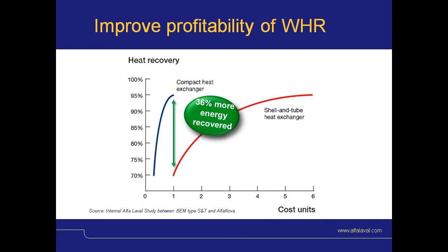Heat exchangers and waste heat recovery play an important role to improve energy efficiency in the process industry. Waste heat recovery means applying heat exchangers to recover energy from process or utility streams and making use of the recovered energy to improve the net energy consumption in a plant. So it means to install heat transfer capacity to capture the energy before it is lost in the drains or to the atmosphere.